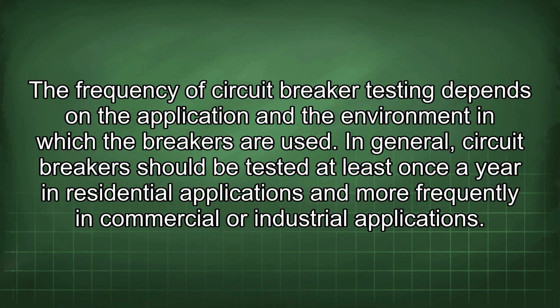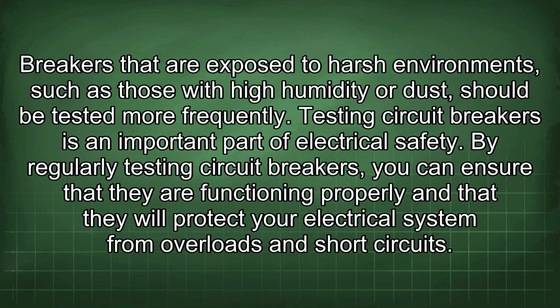In general, circuit breakers should be tested at least once a year in residential applications and more frequently in commercial or industrial applications. Breakers that are exposed to harsh environments, such as those with high humidity or dust, should be tested more frequently. Testing circuit breakers is an important part of electrical safety. By regularly testing circuit breakers, you can ensure that they are functioning properly and that they will protect your electrical system from overloads and short circuits.